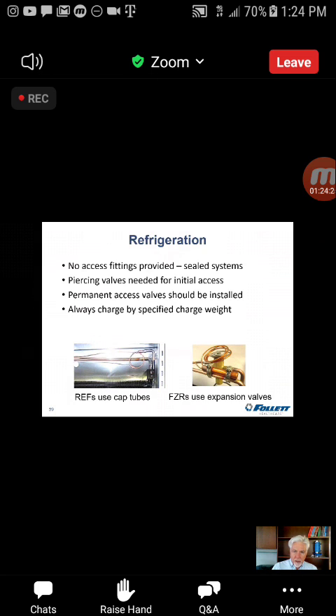There are times with an improperly working refrigeration system when you may be able to get correct pressures with an incorrect charge, and we're hiding a problem. What you need to do is evacuate, charge by weight, and verify that the pressures go to where they're supposed to go. And when they do, your work is done. If they don't, we know we have more work ahead of us. We've got to get in there, identify the problem, and then verify, make sure that we've taken care of everything. So that's it for refrigeration.